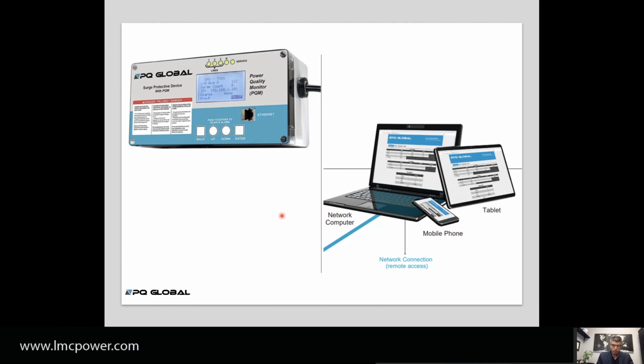The other issue I've seen is some people already have a power quality monitor installed. What we've seen with power quality monitors is, one, they're not cheap — pretty costly if you want a good one. But also, you need a surge protector to protect the power quality monitor itself, since it's pure electronics connected right at the input of the building. Unless that monitor is protected with a surge protector, during large problems it might not give you readings because the little monitor will burn down.